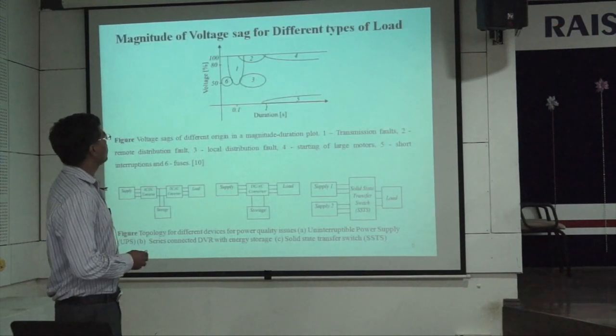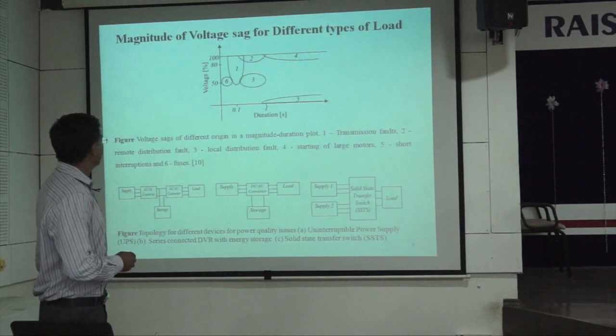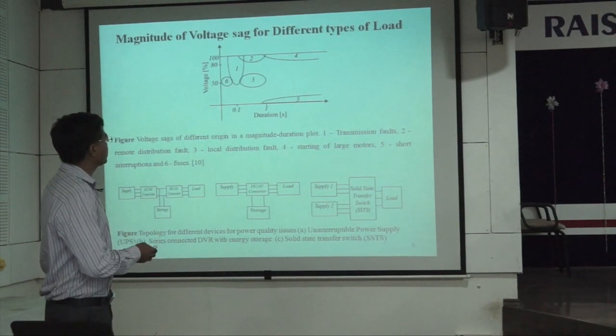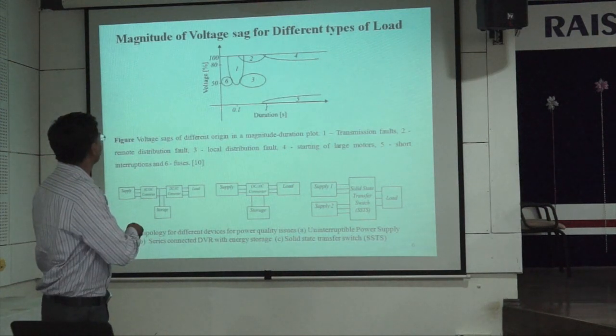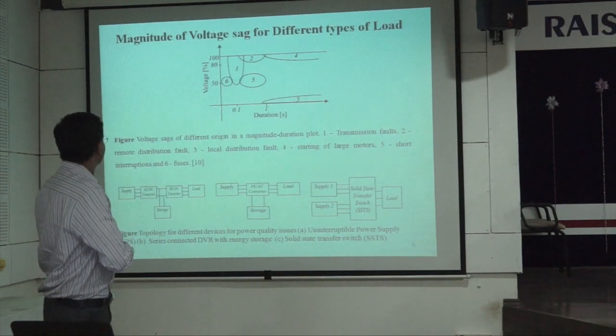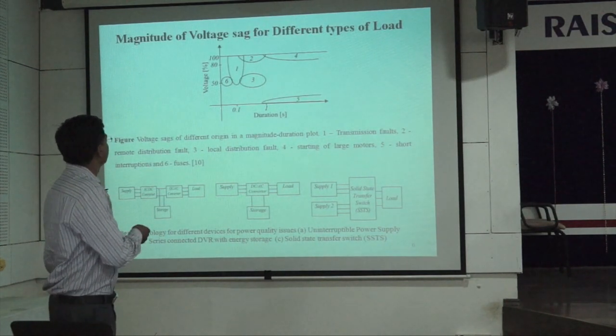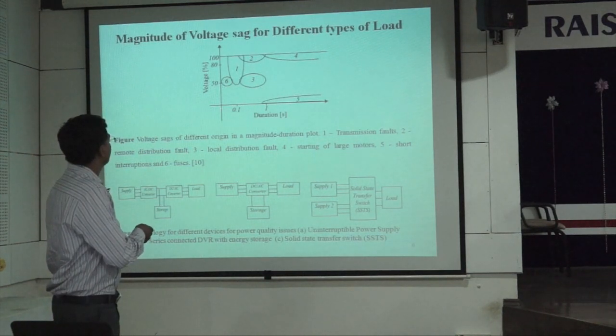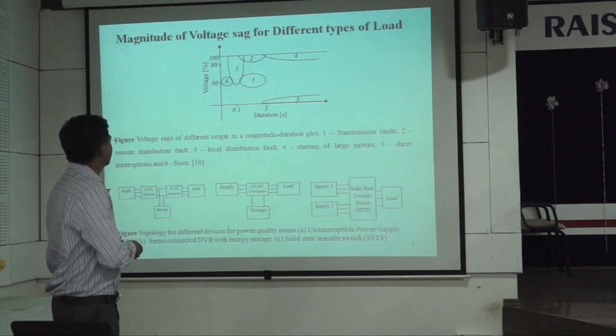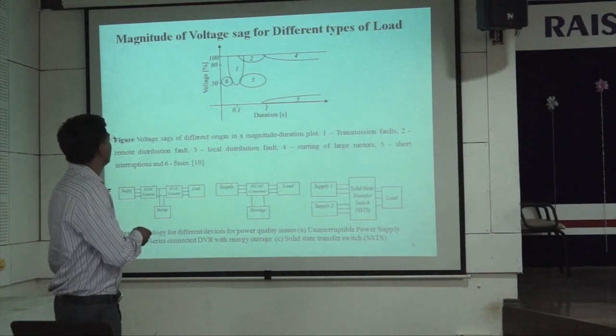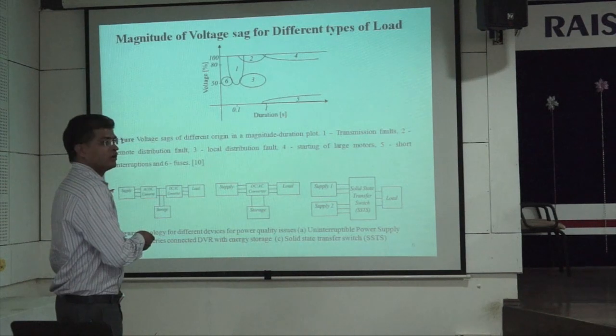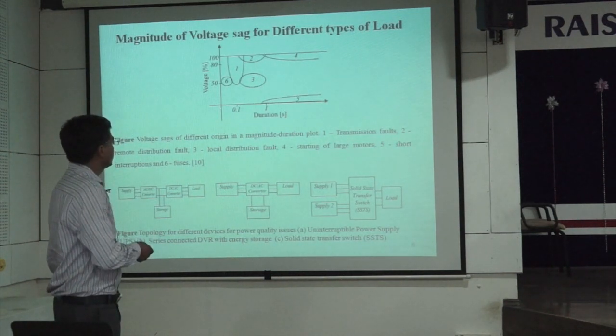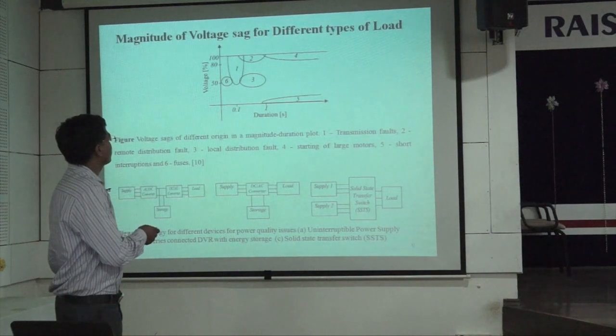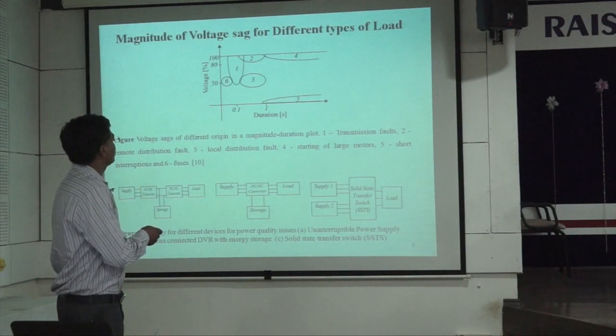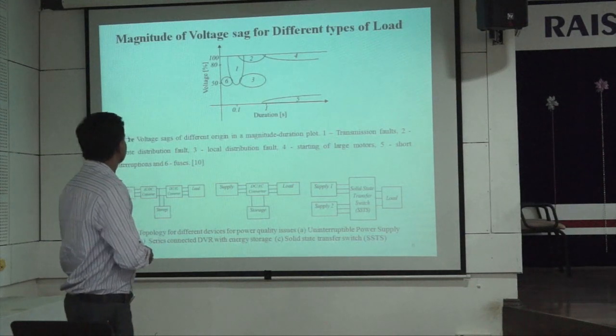So, magnitude of voltage sag for different types of fault. Voltage sag for different origins. Here you can see, one indicates the transmission fault. In transmission fault, the duration is less than 0.2 second. For remote distribution type fault, the sag is not less than 80%. For local distribution fault, the sag is around 50% for a duration of less than 0.8 seconds. And on the starting of a large motor, there is a little bit of sag in the voltage, so we can maintain it without active power injection, short circuit interruption and fuses.